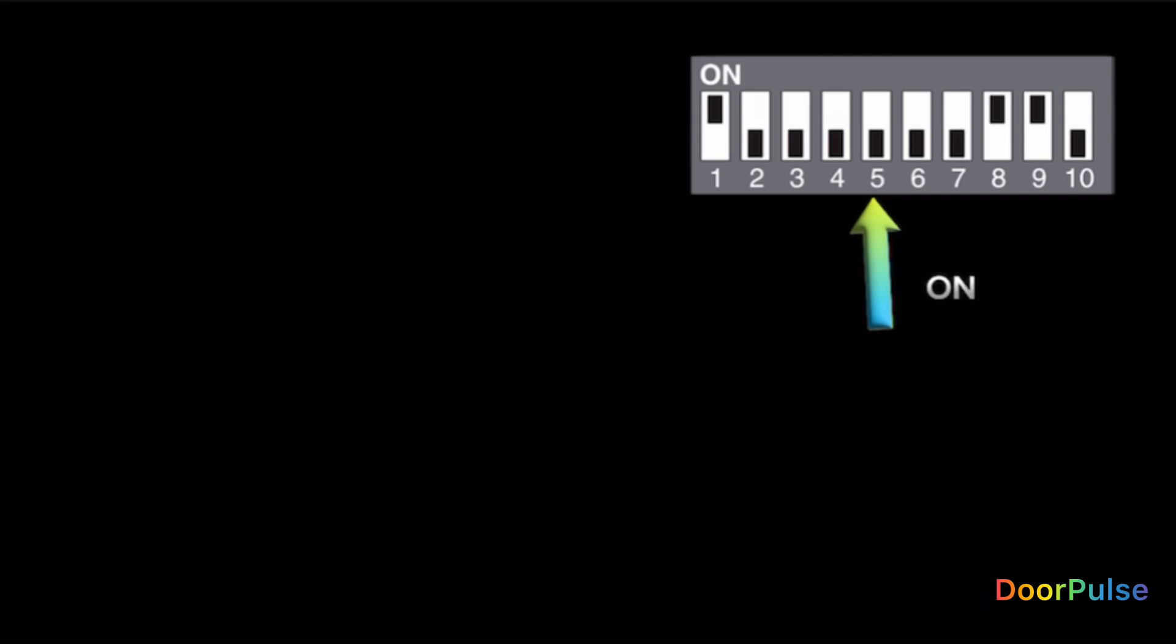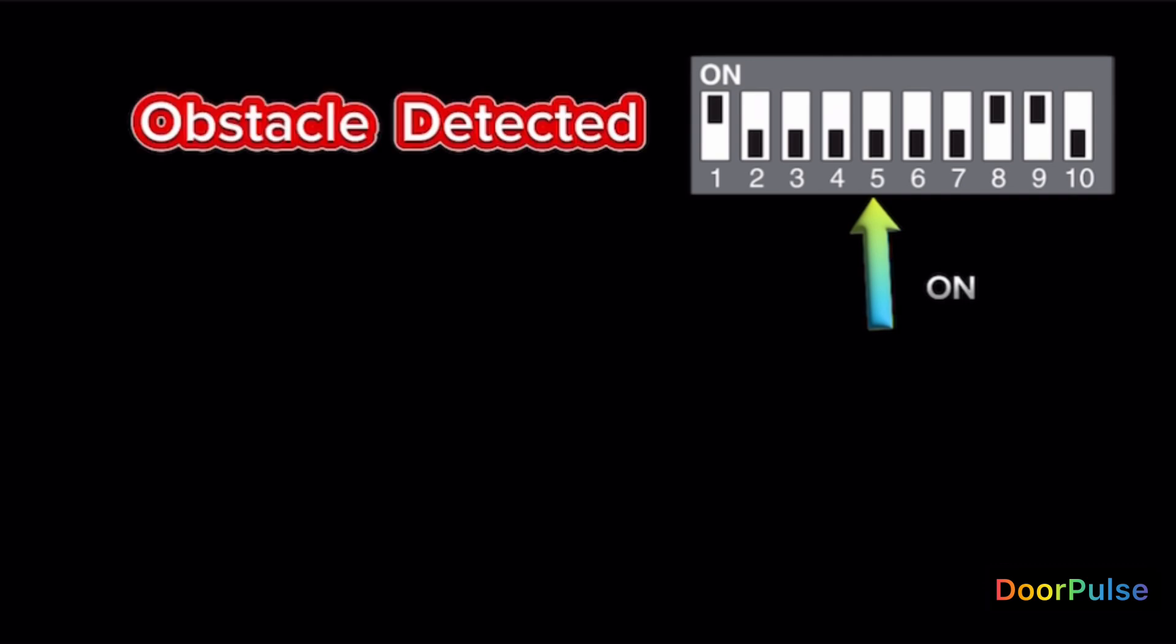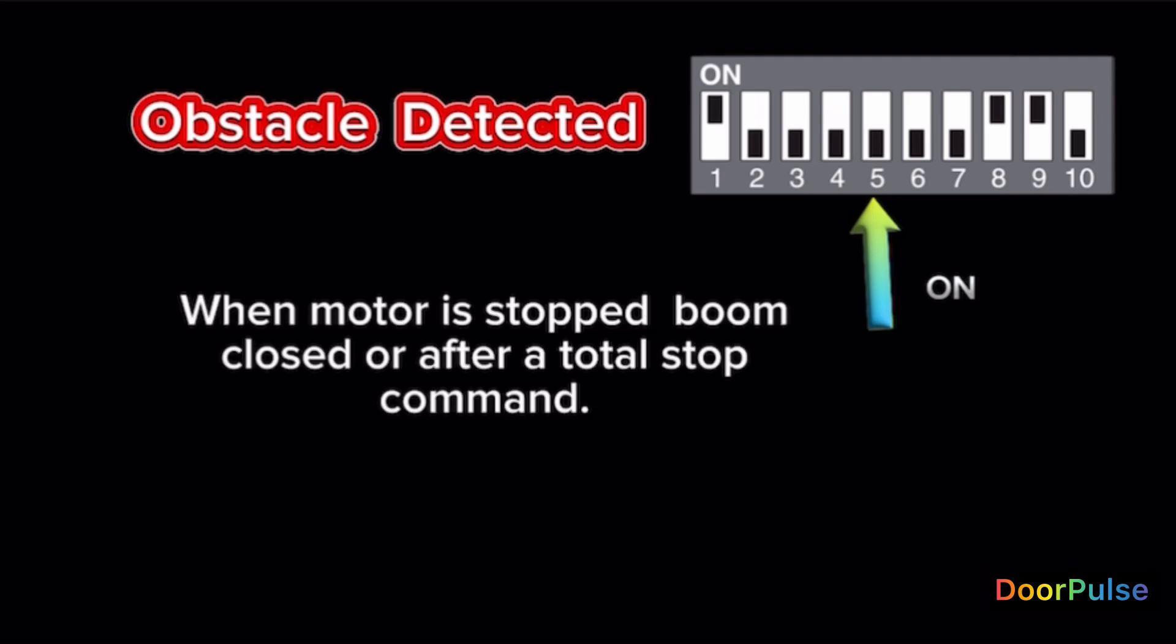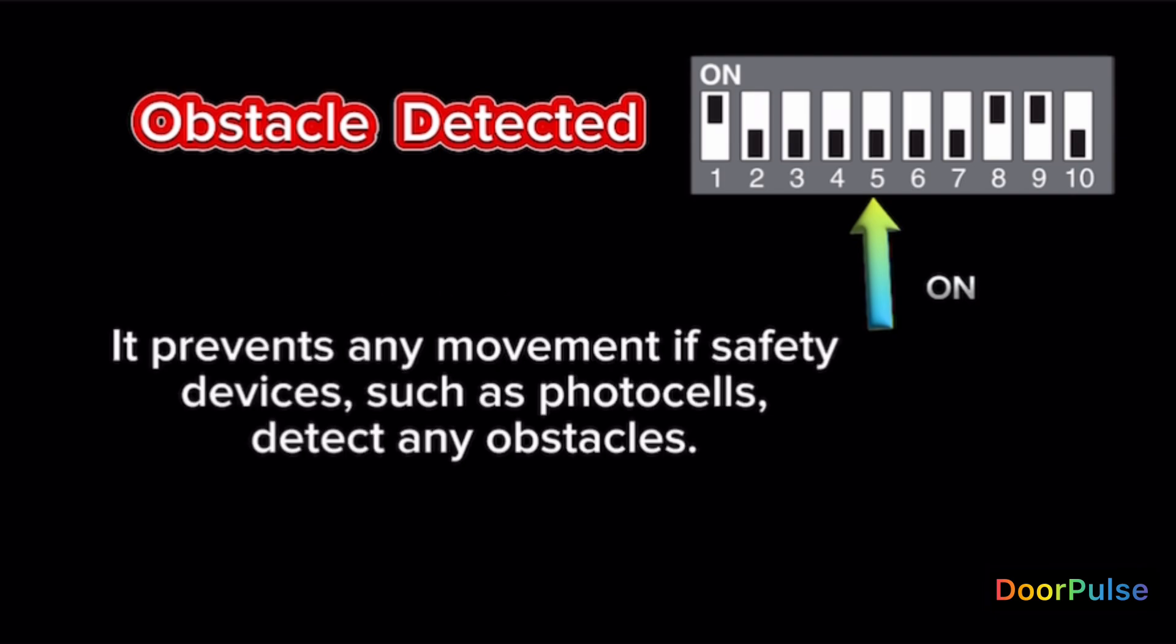Switch 5 ON. Obstacle detected. When motor is stopped, boom closed, or after a total stop command, it prevents any movement if safety devices such as photocells detect any obstacles.